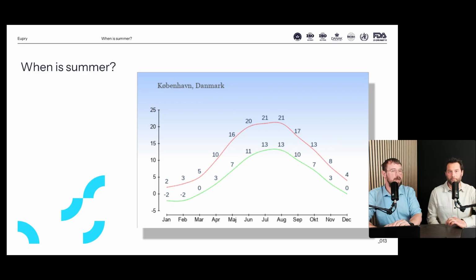Just having a warehouse with a mapping report that says compliant does not mean it will stay that way - that's an important takeaway. The behavior of the unit can change based on seasonality, and the same can happen in winter. That's why in GxP industries it's often required to perform both a summer and a winter mapping during specific periods.